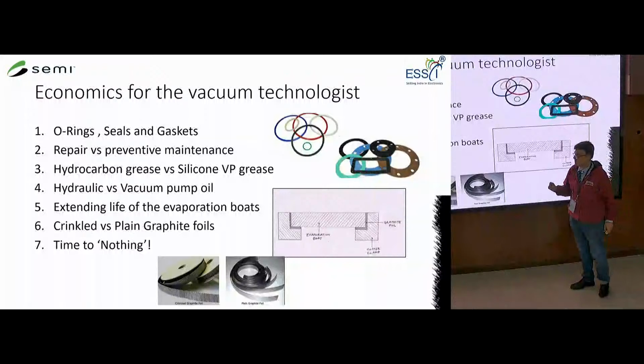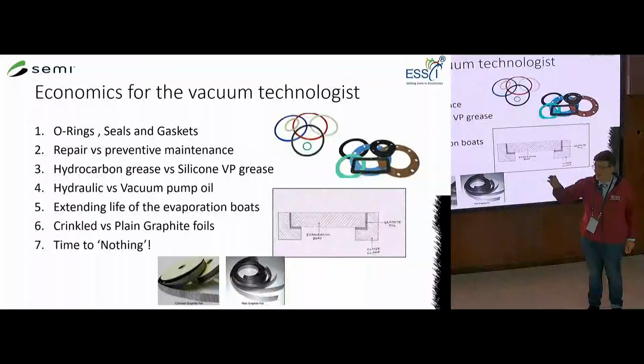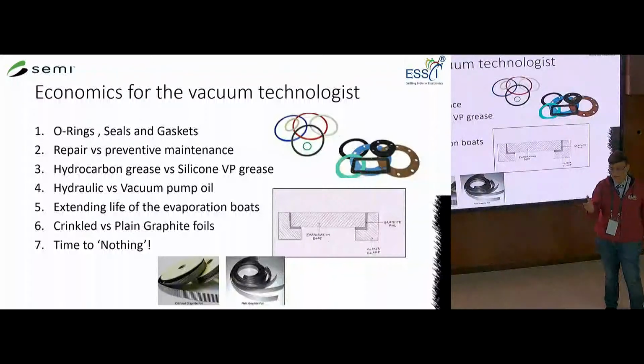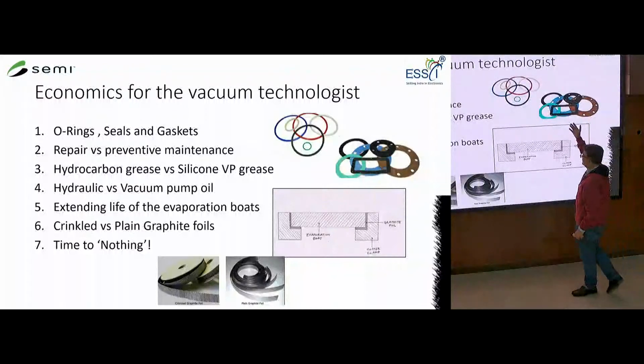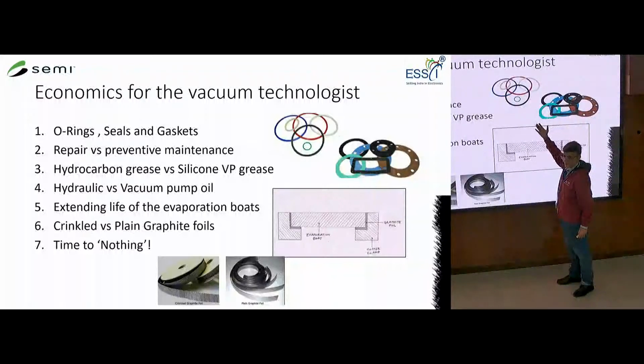In vacuum technology, there are components like O-rings, seals and gaskets. These simply fit on the pipes and hold the seal together. Gaskets sit between two parts of a piping system, enabling contact between them. Imagine if there's a leak at such a joint, it can compromise your entire vacuum creation process.